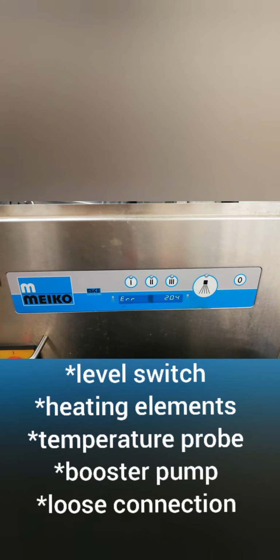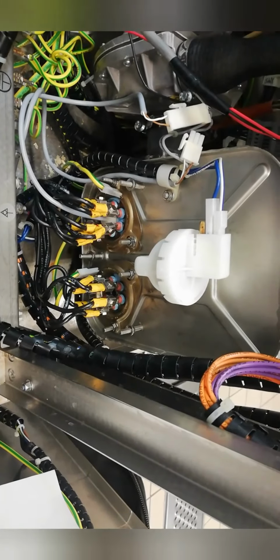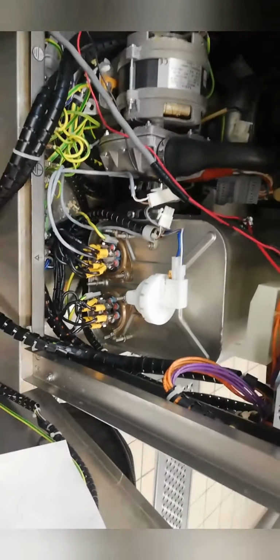Now next up is error 204, which is: following the end of rinse time, still no change detected on the level switch. In this error, you have to check your level switch, the heater on your booster pump, and check for loose connections. Okay, so I checked the level switch by applying pressure on it to check if it's still closing. Well, it's closing. The heaters are newly installed. The temperature probe is okay. The resistance and obstruction on the booster pump are okay as well, but still this error 204 cannot be eliminated. Even when I try to drain it, the error still pops up.